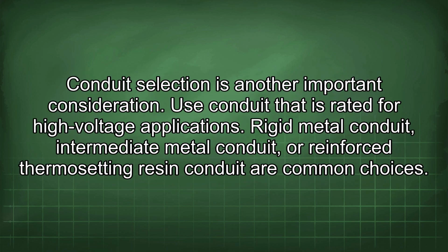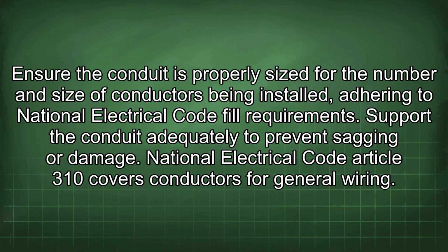Conduit selection is another important consideration. Use conduit that is rated for high voltage applications. Rigid metal conduit, intermediate metal conduit, or reinforced thermosetting resin conduit are common choices. Ensure the conduit is properly sized for the number and size of conductors being installed, adhering to National Electrical Code fill requirements. Support the conduit adequately to prevent sagging or damage.